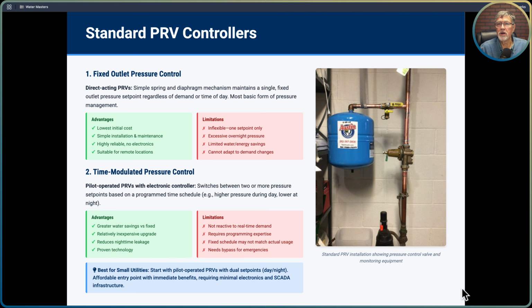So higher pressures during the day when you're getting a lot of use in the system, and lower at night when you're getting less use. So you're maintaining a constant pressure based on the time of day. So you're going to have some historical information on, and you're probably going to have to tweak this a little bit to get the timing right on these things.